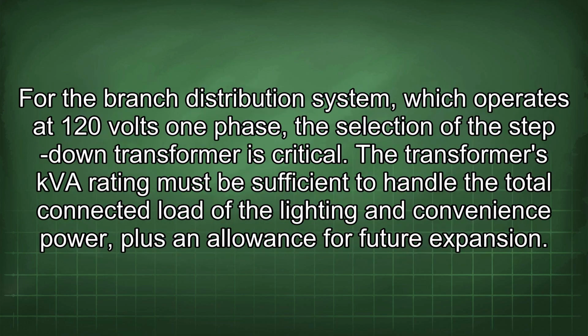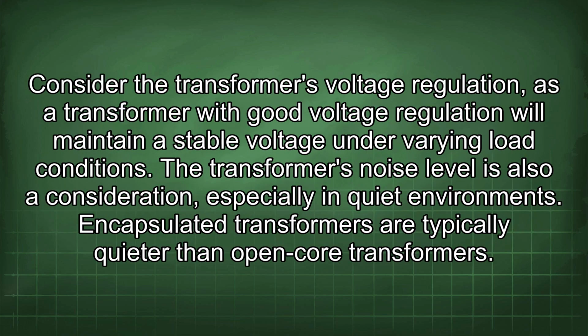For the branch distribution system, which operates at 120 volts one phase, the selection of the step-down transformer is critical. The transformer's kVA rating must be sufficient to handle the total connected load of the lighting and convenience power, plus an allowance for future expansion. Consider the transformer's voltage regulation, as a transformer with good voltage regulation will maintain a stable voltage under varying load conditions. The transformer's noise level is also a consideration, especially in quiet environments. Encapsulated transformers are typically quieter than open-core transformers.